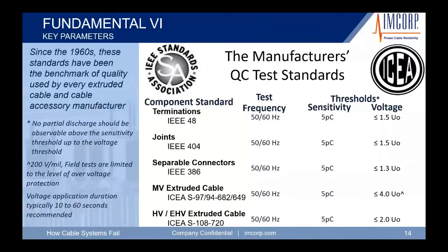Here we know that it's allowed to have 5 picocoulombs of partial discharge in the system at 1.5 times operating voltage, 1.3 times operating voltage on the separable connectors or load break dead front elbows, and then up to 4 times operating voltage on cables. Now, if you have a cable and it passes the IEEE 48, and you put some sort of legacy test on a cable on a new installation, a go, no-go test, a VLF test, where you have extended voltage on a cable system at 2 times operating voltage, well, this will make this 5 pC area of partial discharge begin to grow.